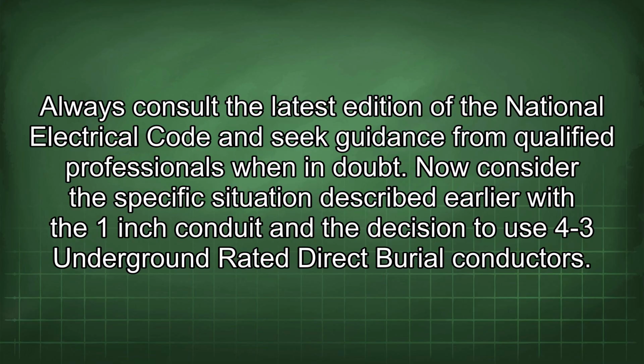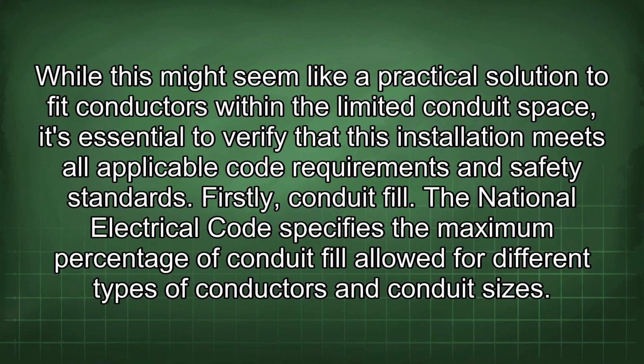Now consider the specific situation described earlier with the 1-inch conduit and the decision to use 4-3 underground rated direct burial conductors. While this might seem like a practical solution to fit conductors within the limited conduit space, it's essential to verify that this installation meets all applicable code requirements and safety standards. Firstly, conduit fill. The National Electrical Code specifies the maximum percentage of conduit fill allowed for different types of conductors and conduit sizes.